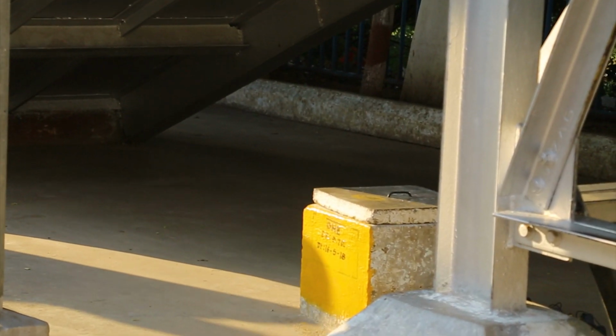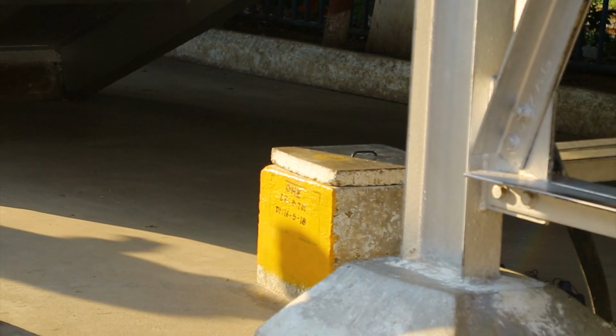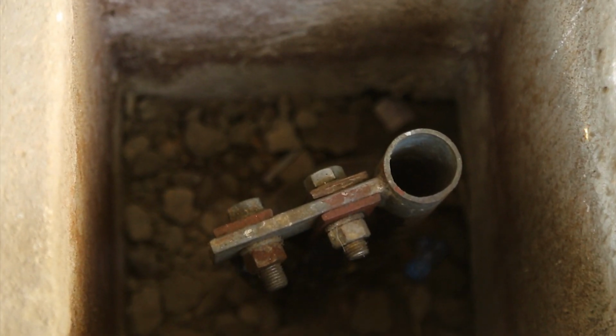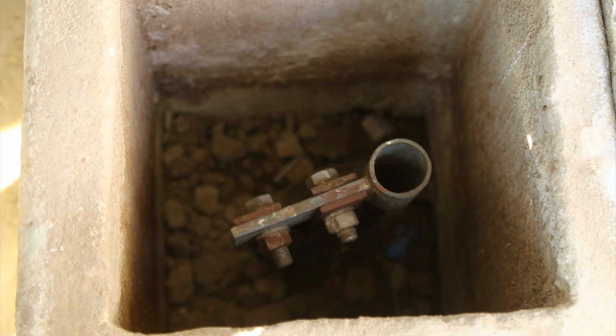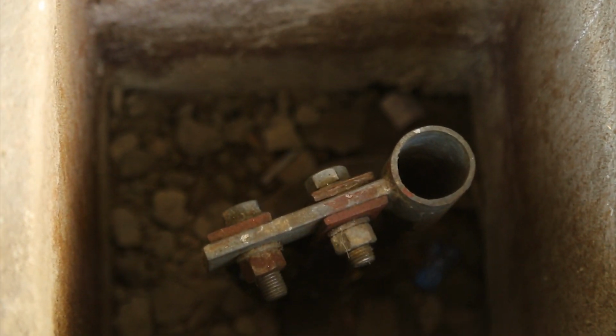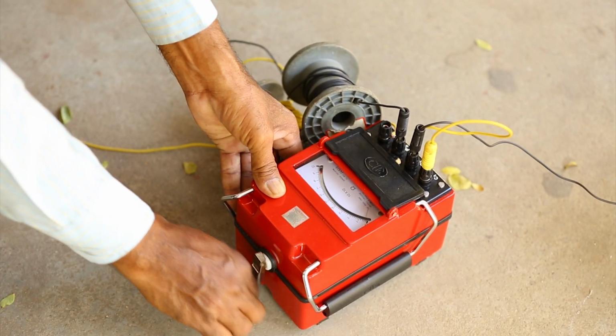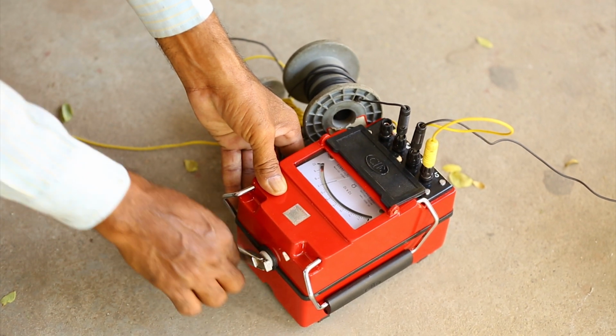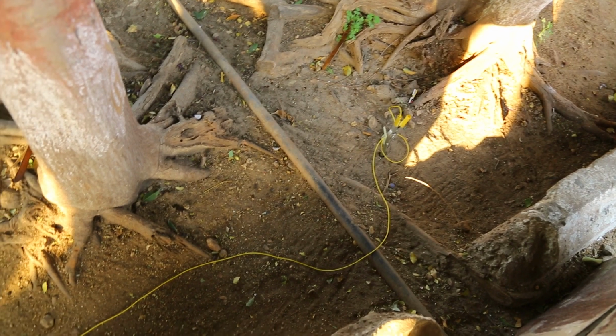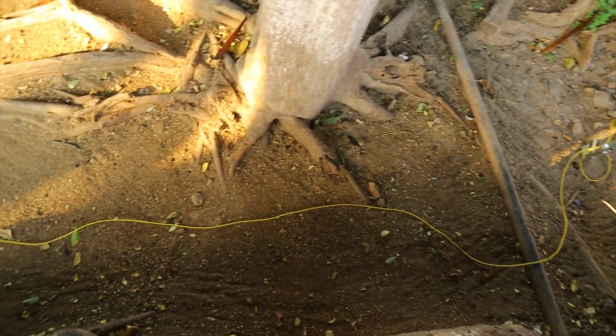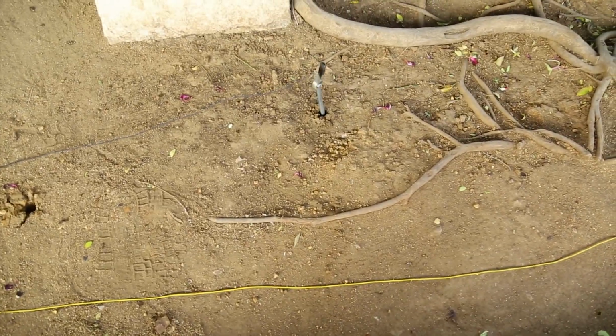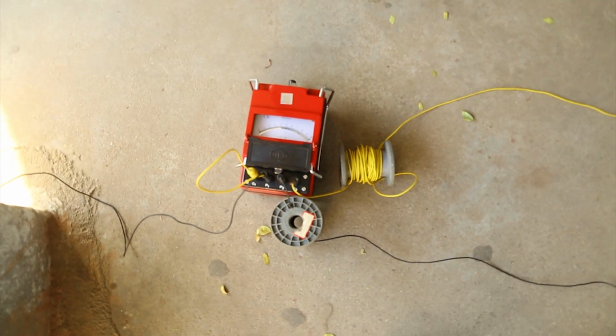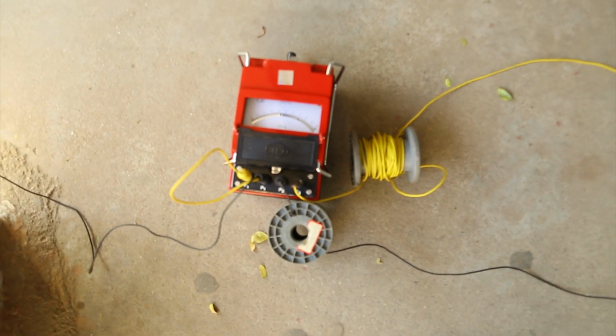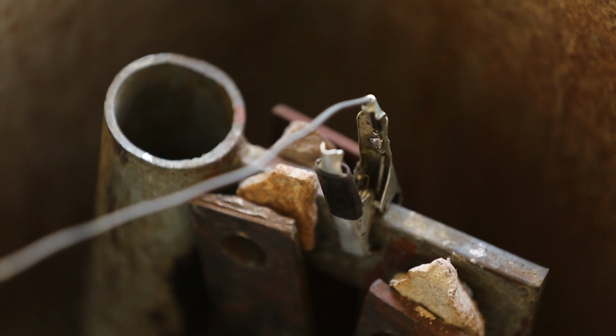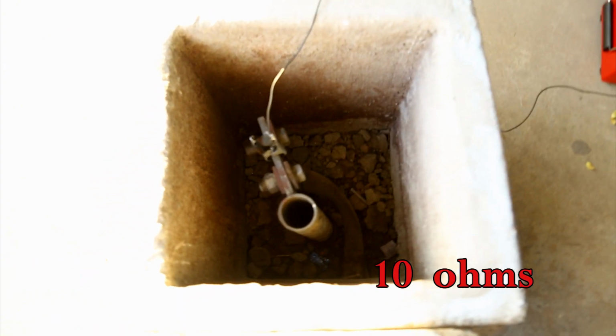Earthing arrangements are provided on railway platforms. This arrangement connects all the metallic structures on the platform to an earth pit having an earth electrode. The resistance at the earth pit is measured using an equipment called Megger. Earthing resistance of FOB, ROB, girders, bridges, platform shed and other overline structures: 10 ohm.